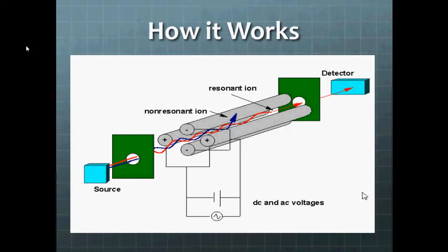So how does it work? The first and third quadrupole work as mass filters based on this setup right here. There's four rods and all four rods have two different voltages applied on them. Two rods have a negative DC voltage applied to them while the other two have a positive DC voltage applied to it, and all four rods have a radio frequency AC voltage applied on them. As ions are being accelerated through the quadrupole, the voltages, both AC and DC, are scanned simultaneously.